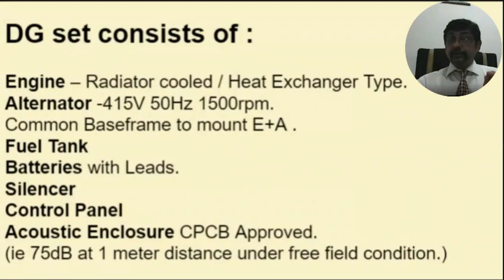Then the alternator is 415 volts, that is the Indian line voltage, 415 volts for the generator. The grid has 440 volts, but the generator runs on 415 volts. Of course, the frequency is 50 hertz. This alternator has a regulator, that is the AVR, automatic voltage regulator, which has a regulation of 2 to 2.5%, probably up to 5% it can regulate. So in case of any jerk load or torque load, where the voltage shoots up or comes down, the voltage regulator ensures the line voltage comes again to 415 volts.